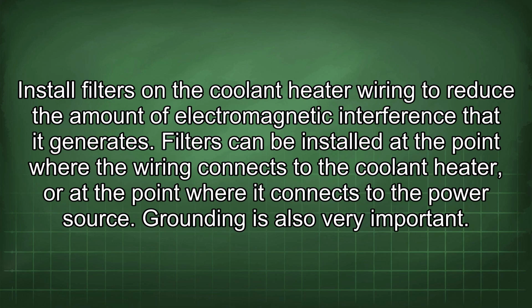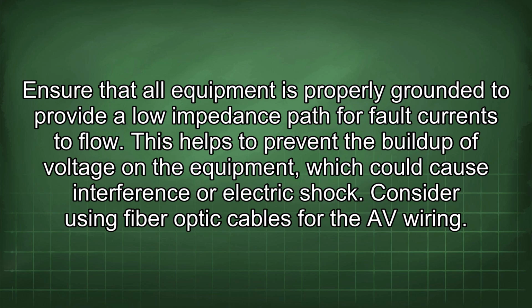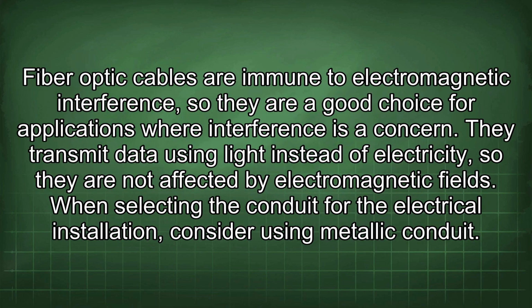Grounding is also very important. Ensure that all equipment is properly grounded to provide a low impedance path for fault currents to flow. This helps to prevent the buildup of voltage on the equipment, which could cause interference or electric shock. Consider using fiber optic cables for the AV wiring. Fiber optic cables are immune to electromagnetic interference, so they are a good choice for applications where interference is a concern. They transmit data using light instead of electricity, so they are not affected by electromagnetic fields.